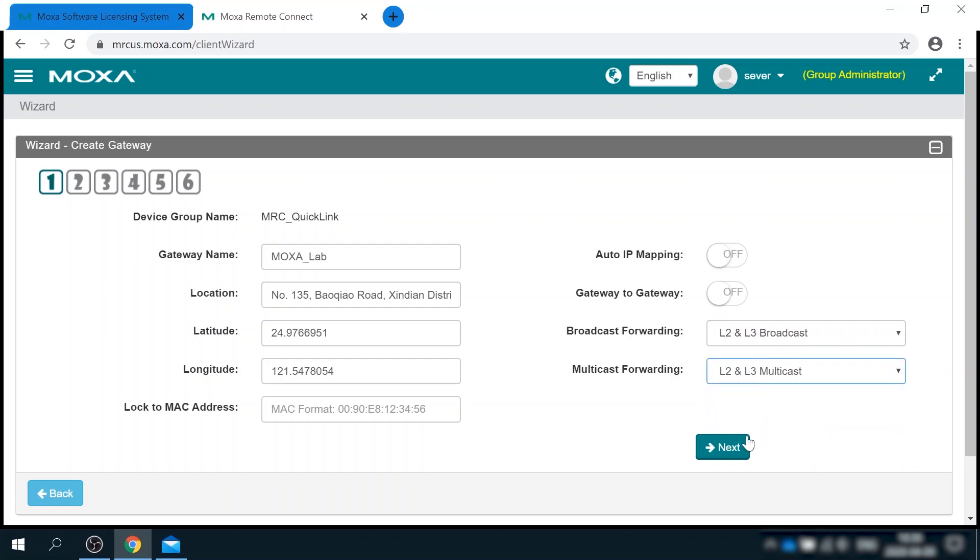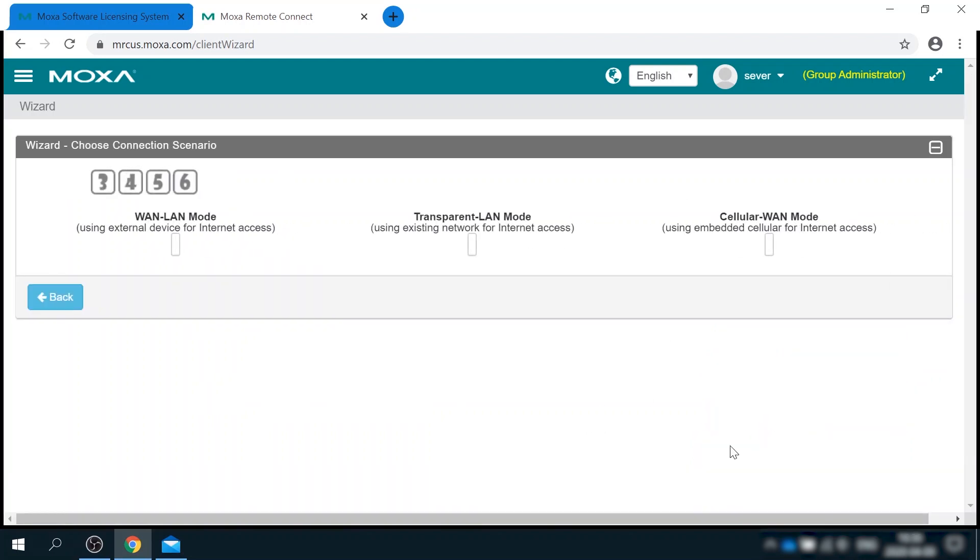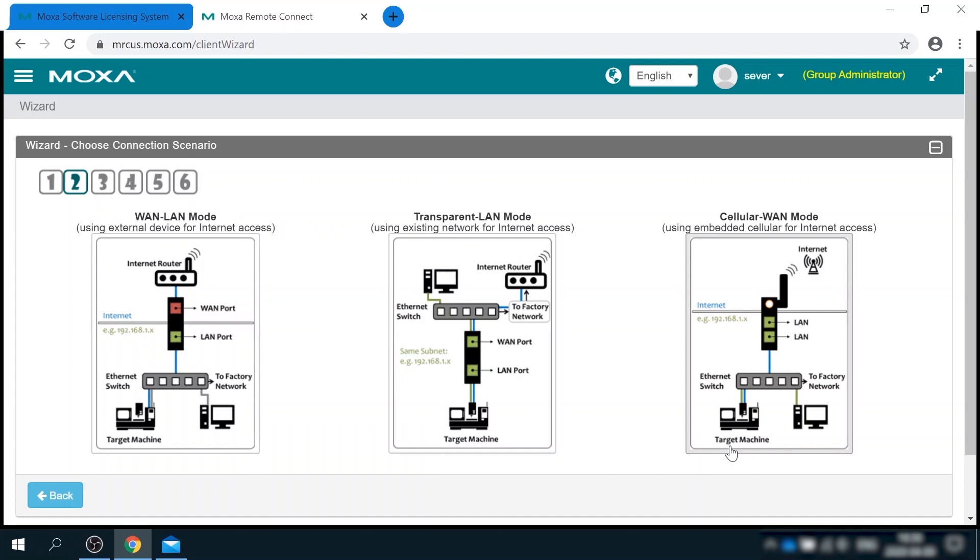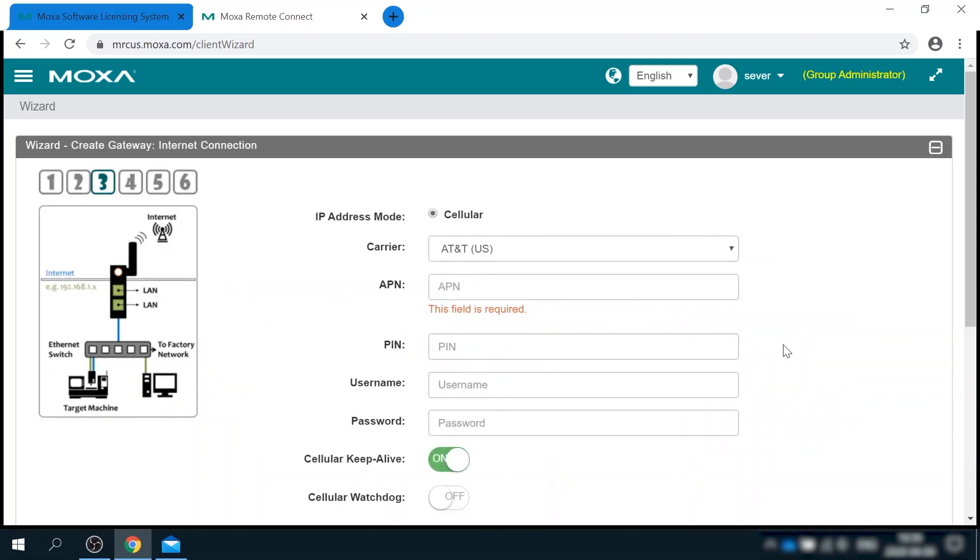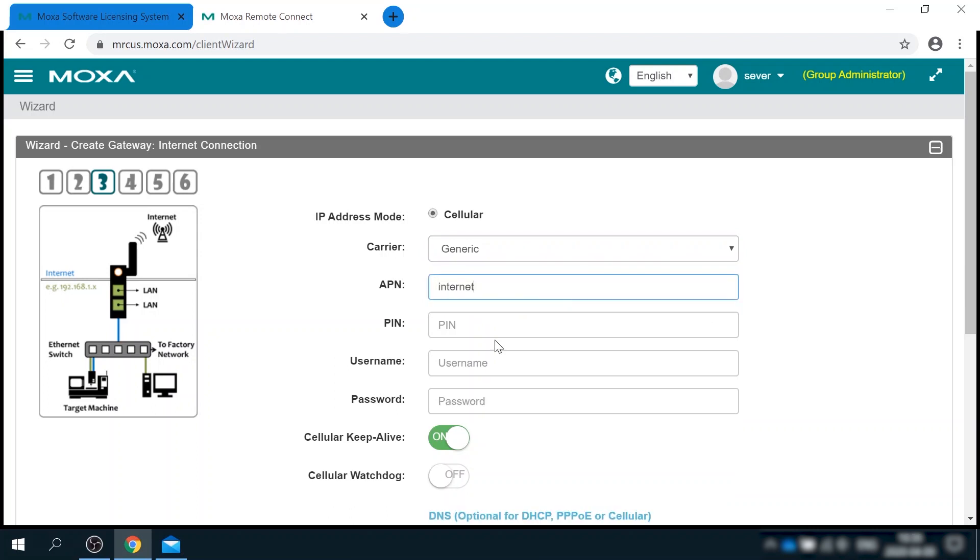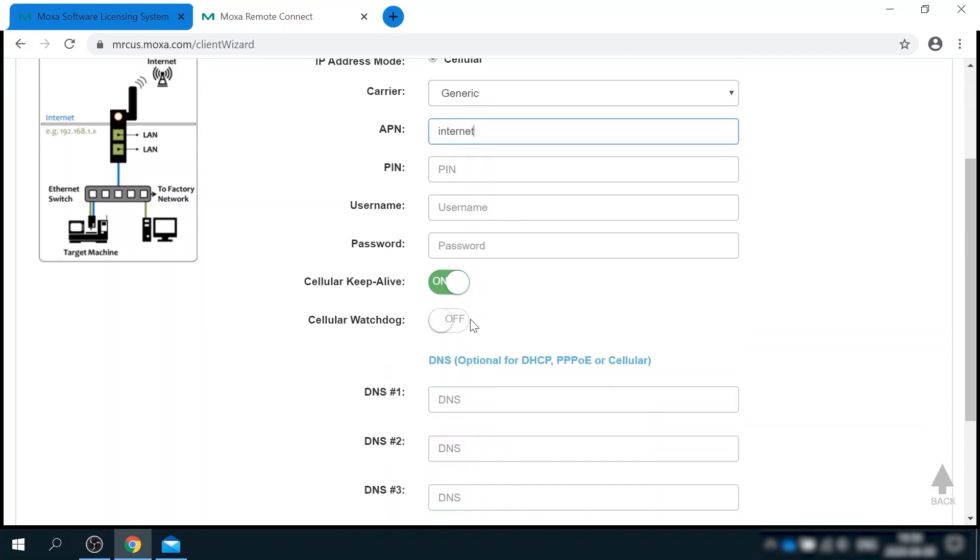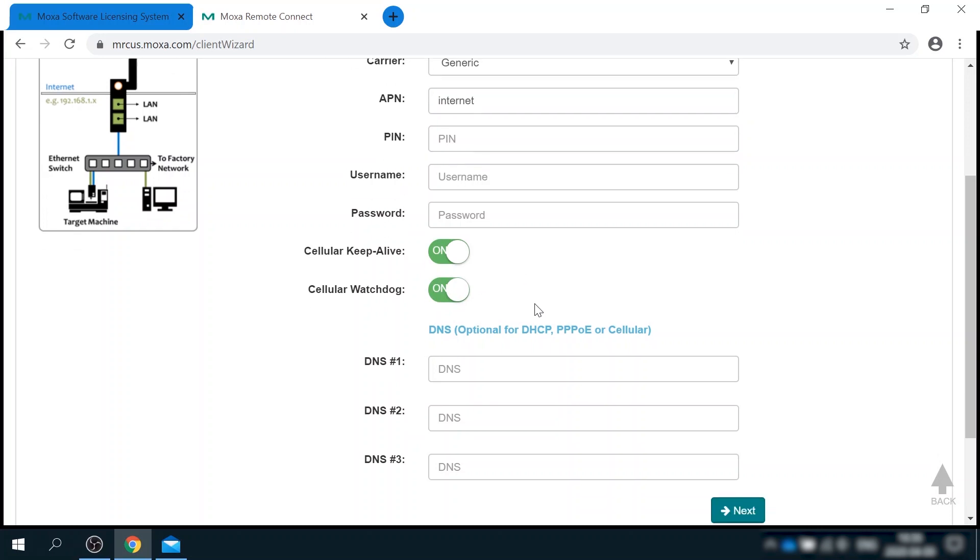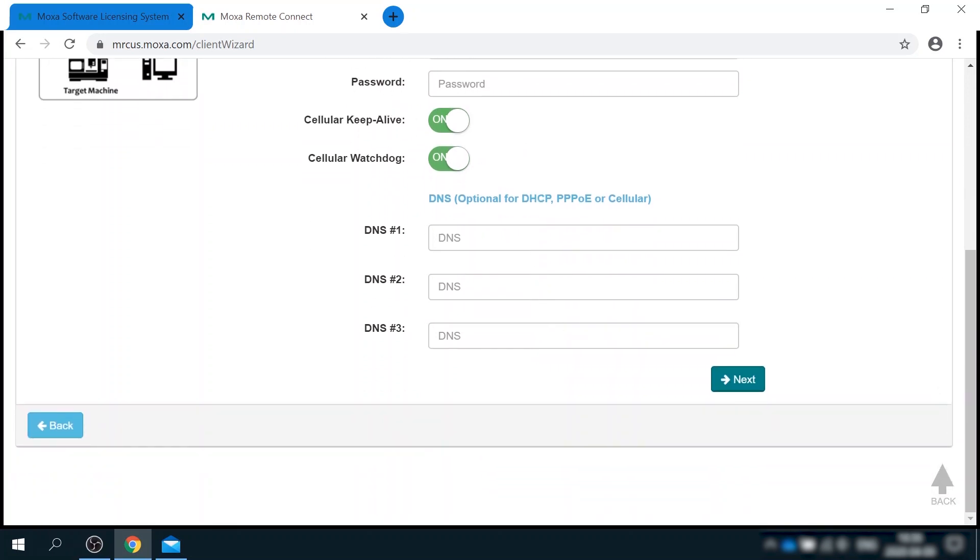Since I'm going to use cellular for internet access, the scenario here is cellular WAN mode. I'm going to use local ISP and I know that its APN value should be internet. And I want to enable cellular watchdog just in case of any connectivity issues. This will basically reboot gateway if cellular fails.